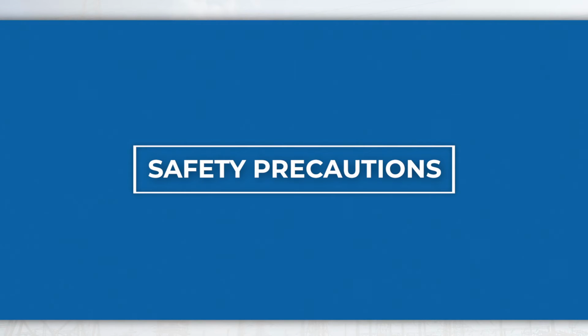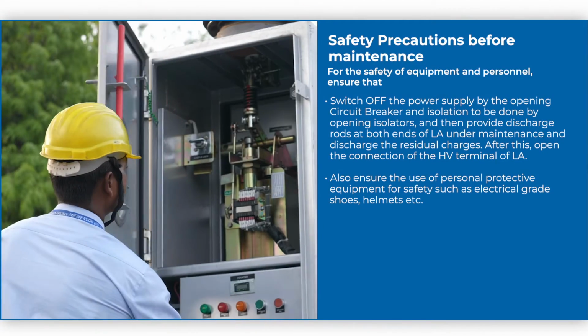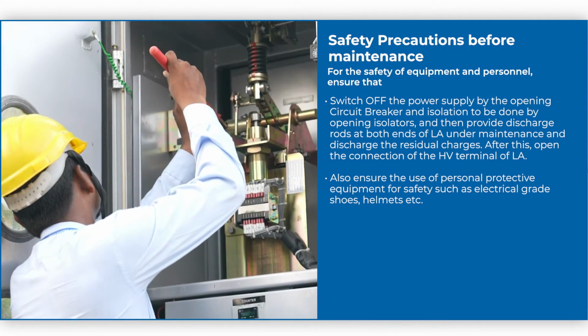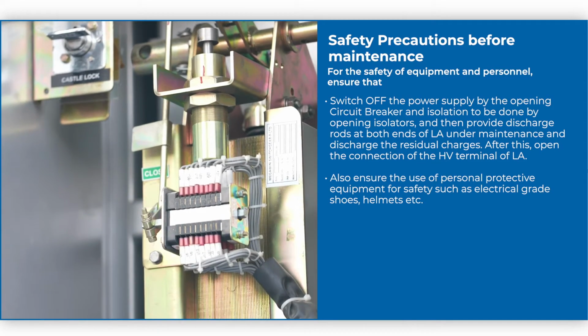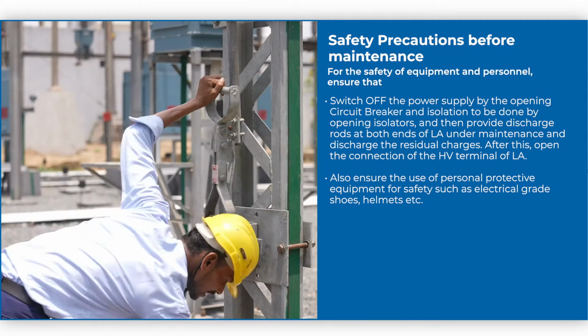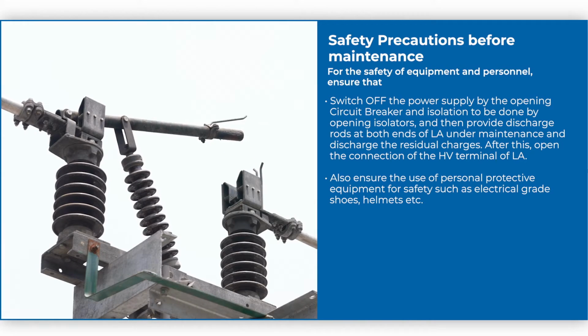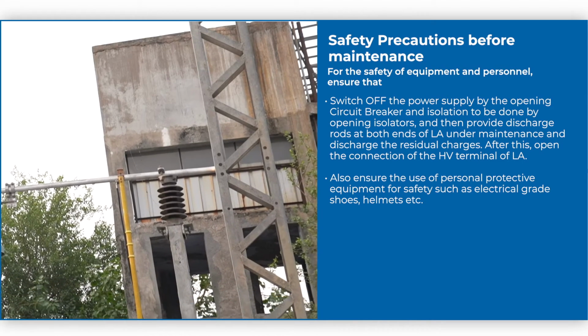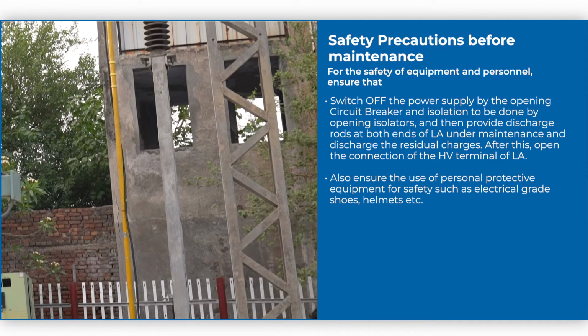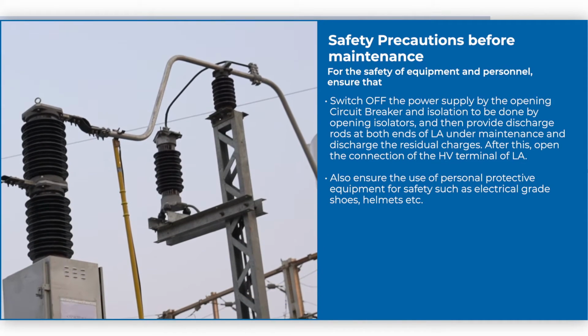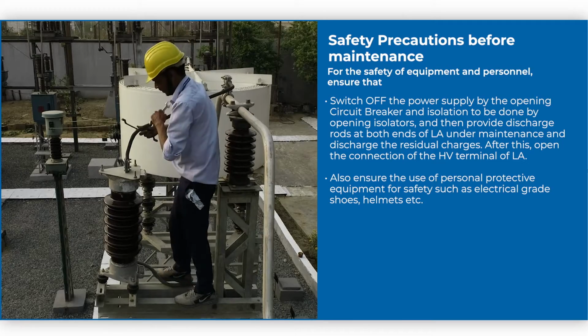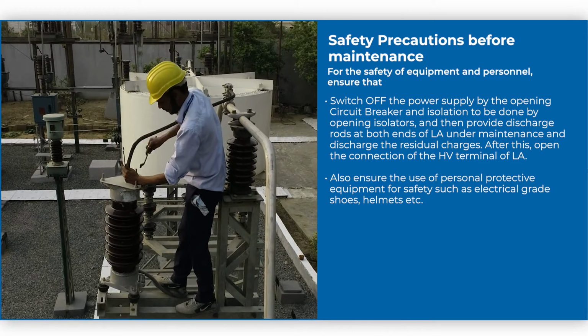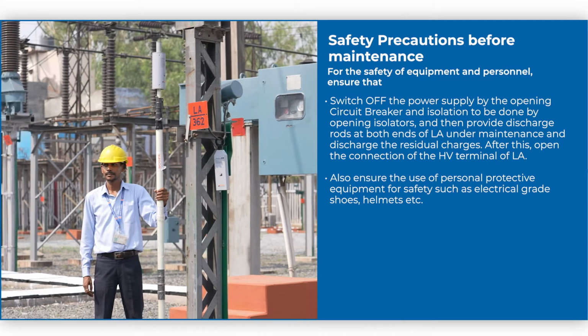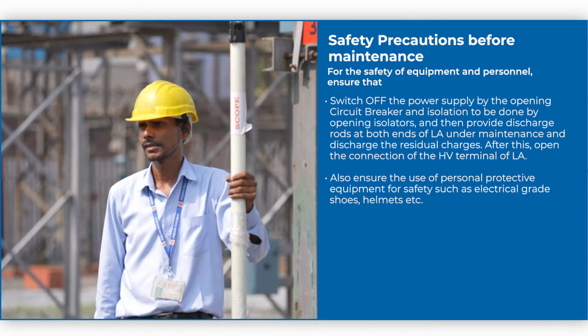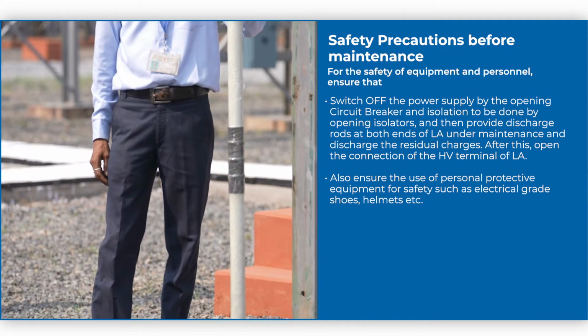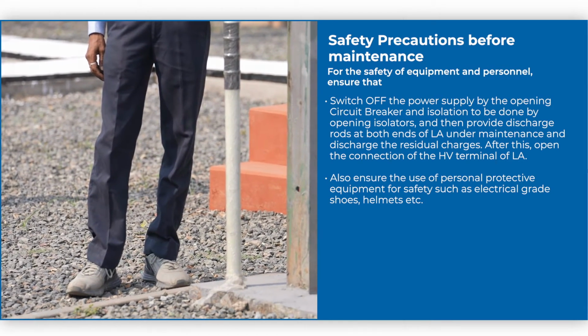Safety precautions before maintenance. For the safety of equipment and personnel, ensure that the power supply is switched off by opening the circuit breaker and isolation is done by opening isolators, and then provide discharge rods at both ends of the LA under maintenance and discharge the residual charges. After this, open the connection of the HV terminal of LA. And also ensure the use of personal protective equipment for safety such as electrical grade shoes, helmets, etc.